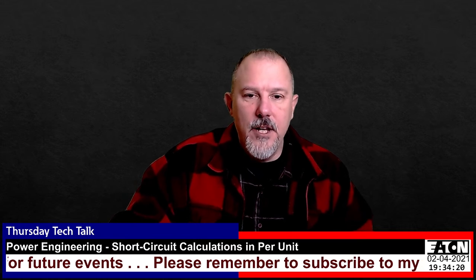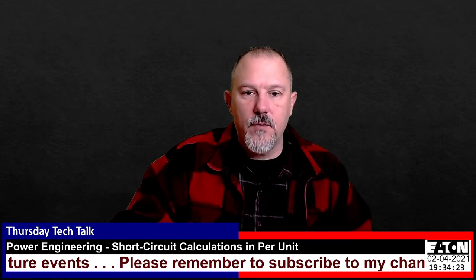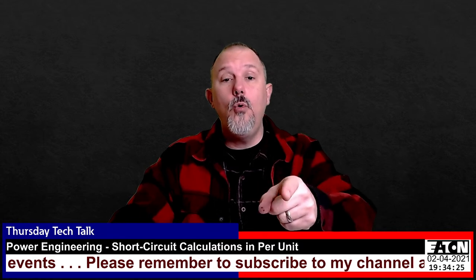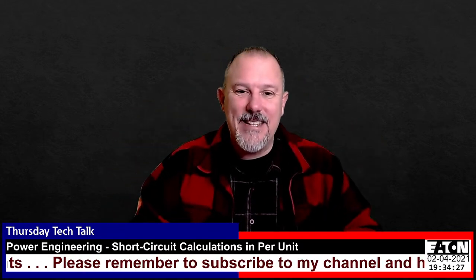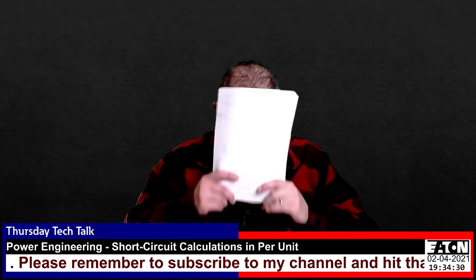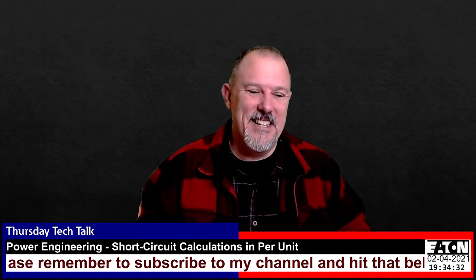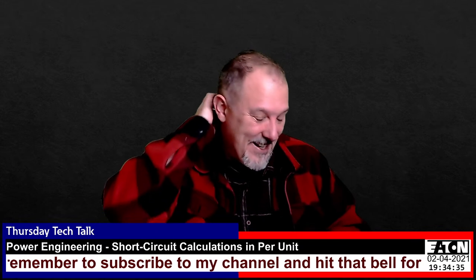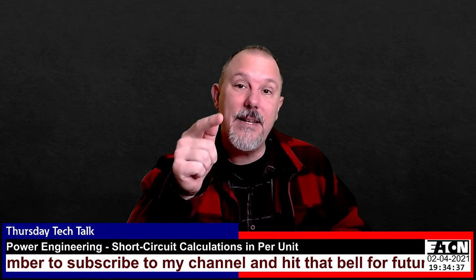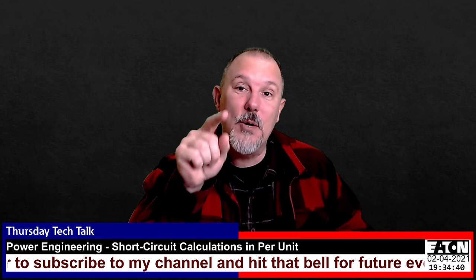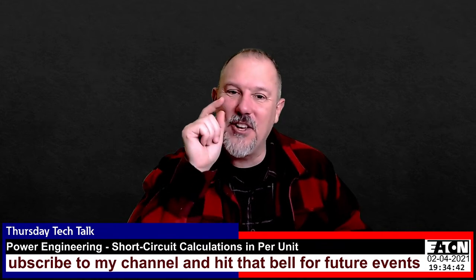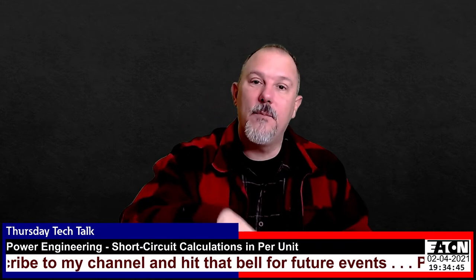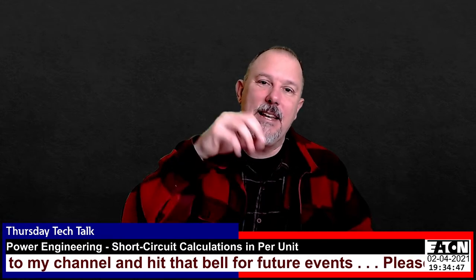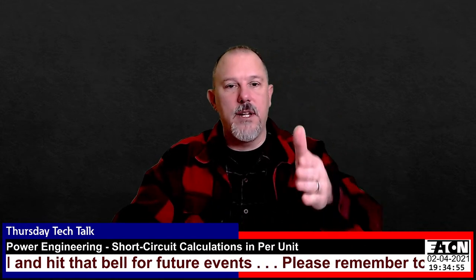Jack Ma, I think that he used 600 volt cables for the primary of transformer, should be 15 kV. Oh, Jack, you are right. Yes, and we're going to look at that too, and at what impedance we use for those cables. Very good catch. But remember, this was an exercise in the math to get those done. I'm showing all of Ahmed's calculations, and I really appreciate him doing that.